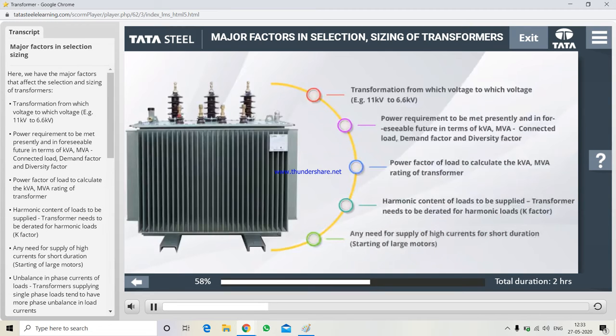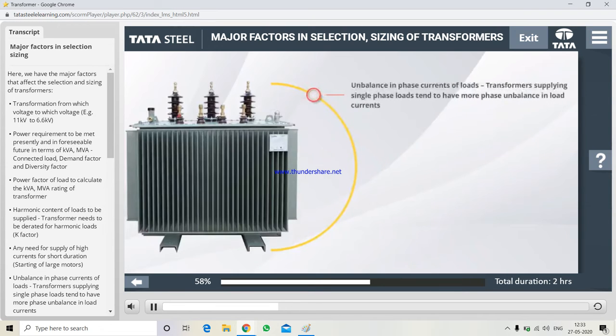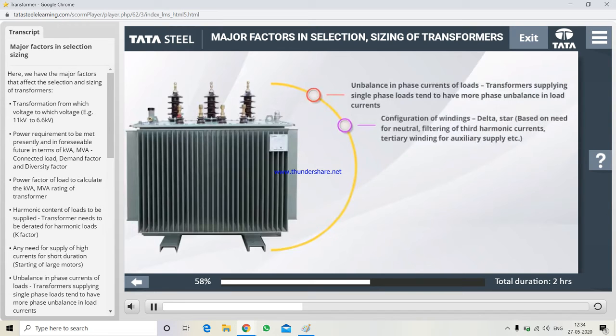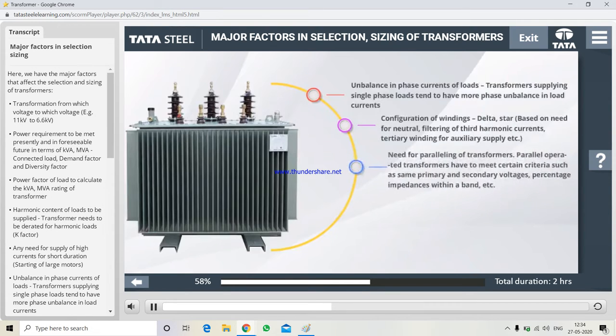Any need for supply of high currents for short duration. Unbalance in phase currents of loads. Transformers supplying single phase loads tend to have more phase unbalance in load currents. Configuration of windings. Delta, star. Based on need for neutral, filtering of third harmonic currents, tertiary winding for auxiliary supply, etc. Need for paralleling of transformers.